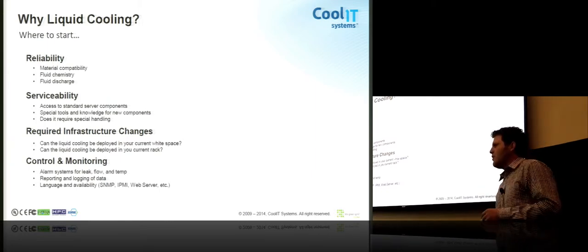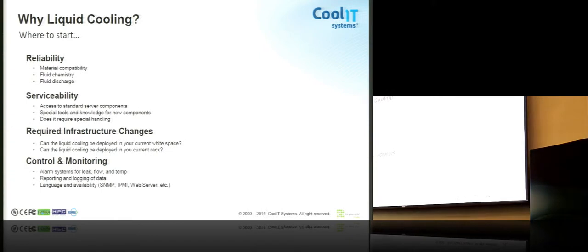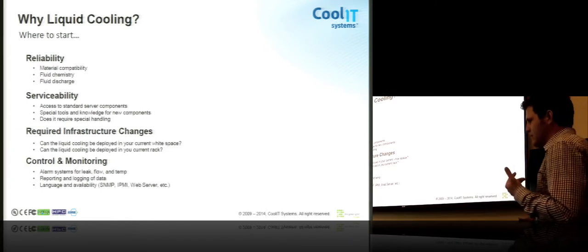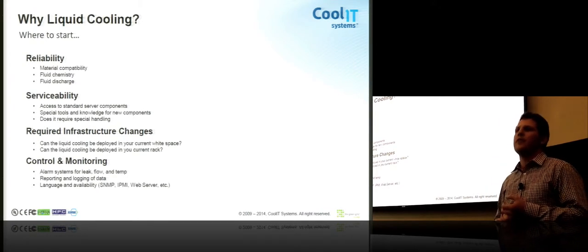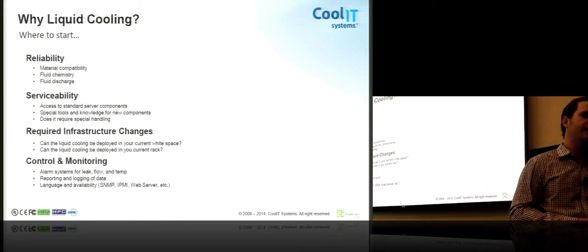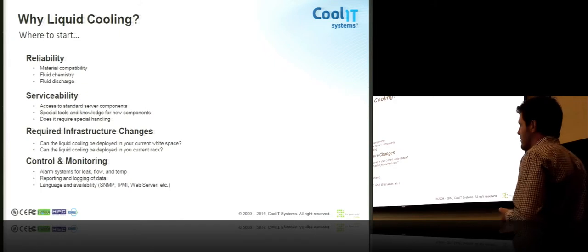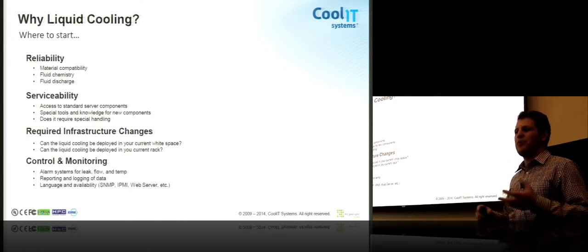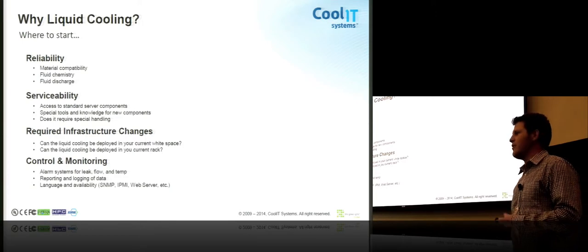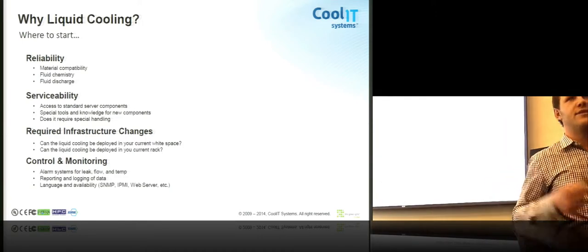So a few more things that you want to talk to your liquid-cooling vendors about as you're sort of scoping out the landscape is number one, reliability. There's lots of discussion on material compatibility and fluid chemistry. So a mixing of certain metals inside the system, as well as the type of fluid that you're going to have circulating. So we need to be careful for fouling, for corrosion, for scaling. Anybody who's been in the space for a long time should have a pretty good answer for that. They should be able to show you all the different materials they use. They should have compatibility studies done.